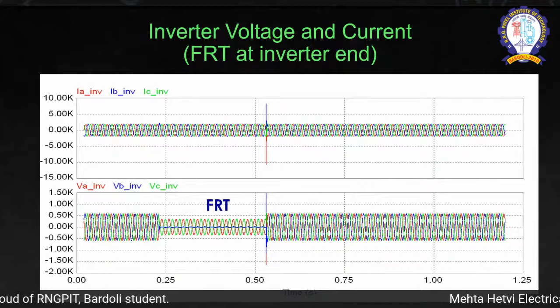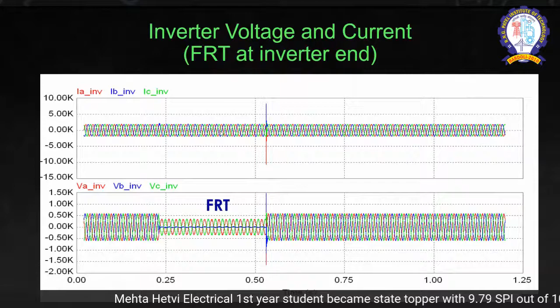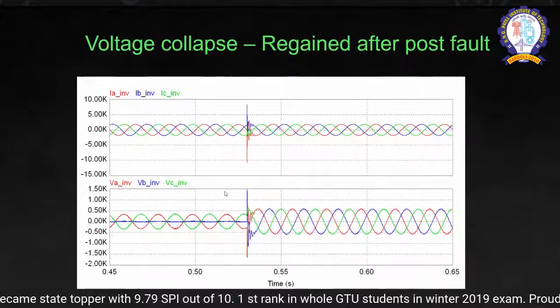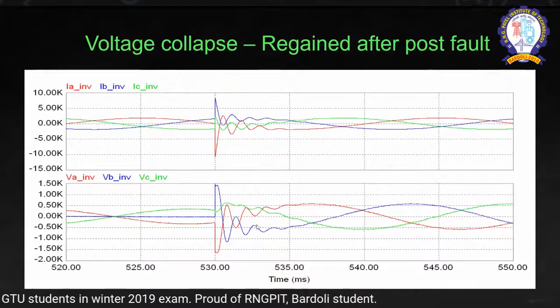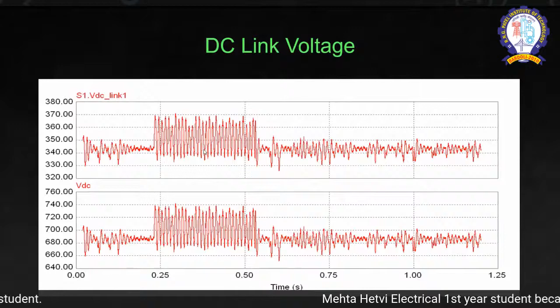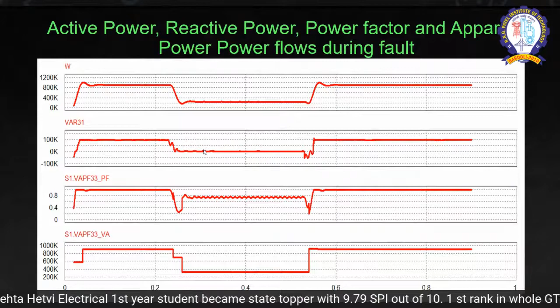However, the grid connection is tightly connected, so there is no collapse in the current; there is a collapse in the voltage, known as the FRT. Now, if you zoom in, it is still less than the tripping time of the relay. So again, the relay will not trip over here. And this is the rise in DC link voltage during fault time. And these are the active and reactive power flows at the fault time and the VA capacity of the machine.